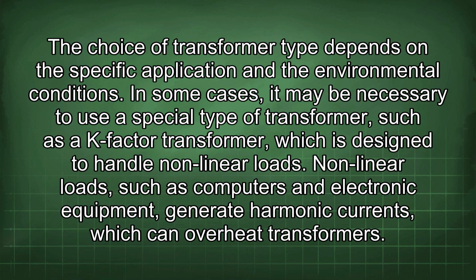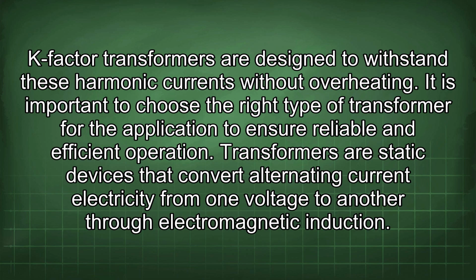In some cases, it may be necessary to use a special type of transformer, such as a K-factor transformer, which is designed to handle nonlinear loads. Nonlinear loads, such as computers and electronic equipment, generate harmonic currents, which can overheat transformers. K-factor transformers are designed to withstand these harmonic currents without overheating. It is important to choose the right type of transformer for the application to ensure reliable and efficient operation.